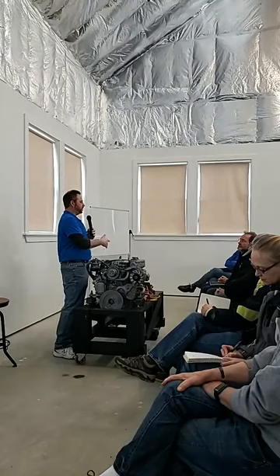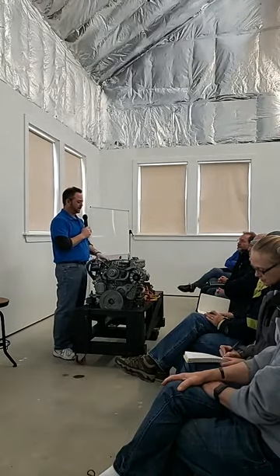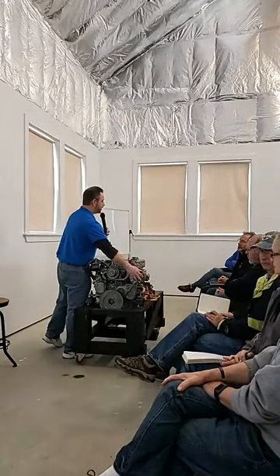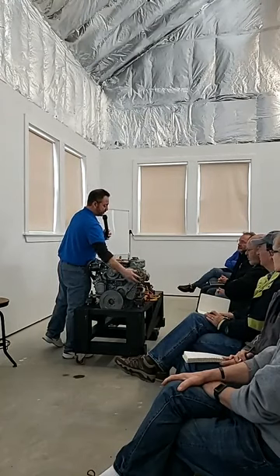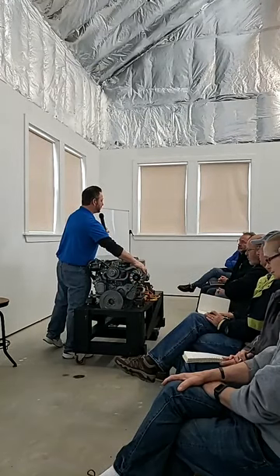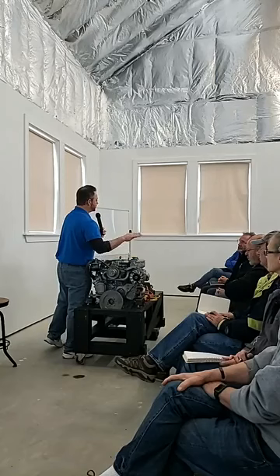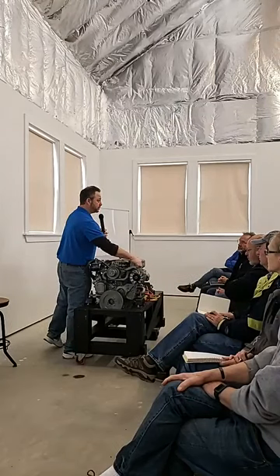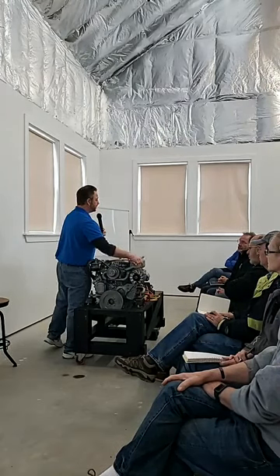We're looking for temperatures below 130 degrees. The cooler the better, so 120 to 100 degrees is an okay zone. Once you start climbing closer to 130, that's when you'll start seeing smoking problems. Not only do we have smoking issues, but our alternators have fans on them to cool them down. Once the engine room gets too hot, the fan doesn't cool the alternator efficiently, and it starts damaging it.